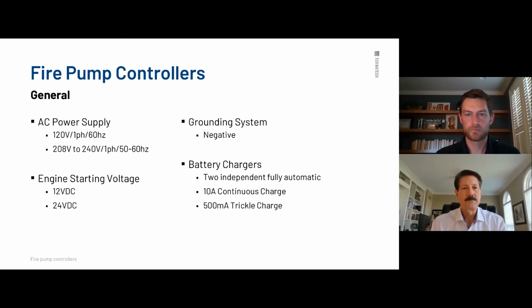Is it 120 or 240 or 208 volt for the incoming AC? And again, you don't see positive ground anymore. That's old. Probably still some out there, but it's a negative ground system. The key here, you have two battery chargers independently automatic of each other. They're 10 amp continuous charge. So if your batteries are really, really low, it goes into a bulk charge. It will lay in 10 amps continuous charge into those batteries until they reach a certain level. The trickle charge, which is just a maintenance or minimum charge, it's a half amp, 500 milliamp trickle.